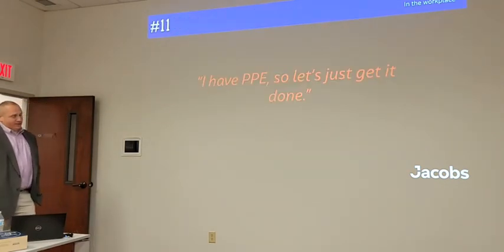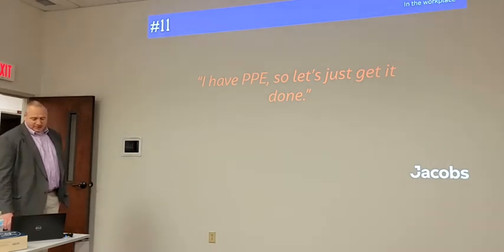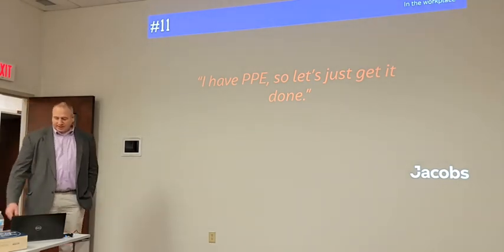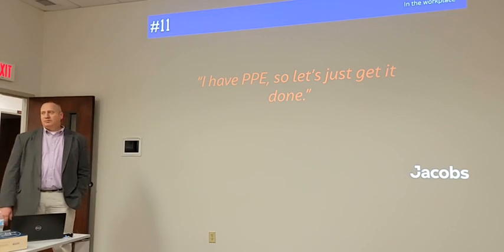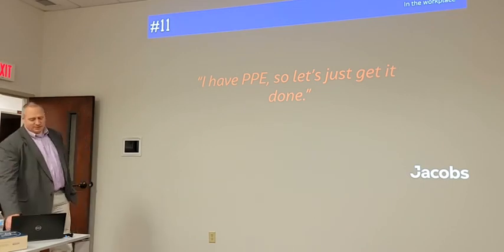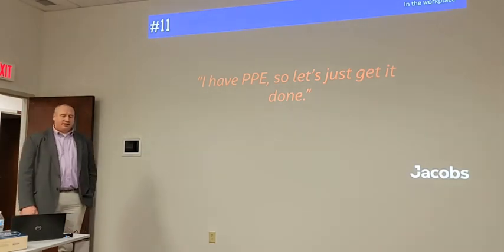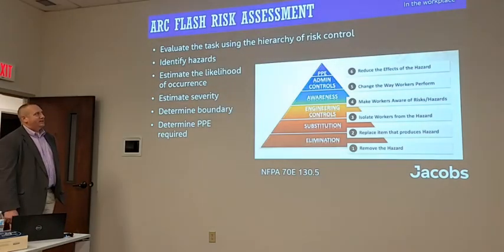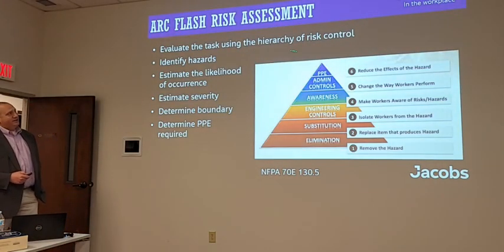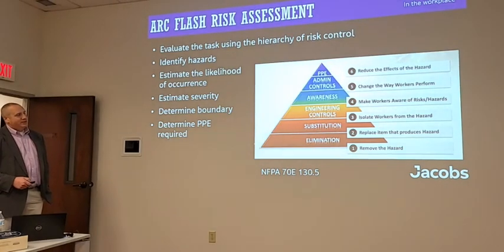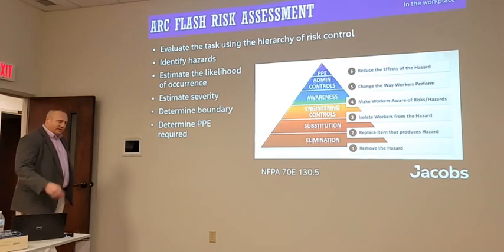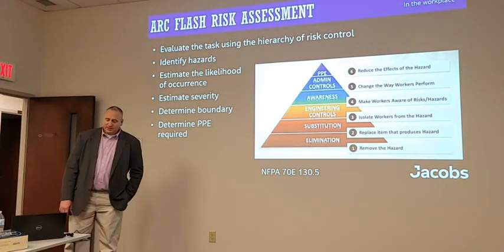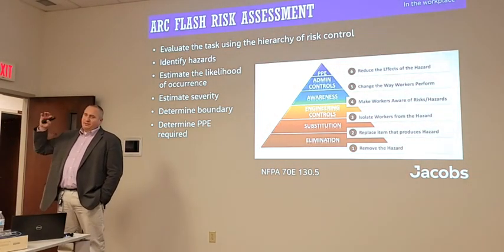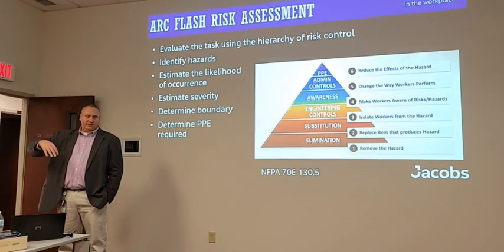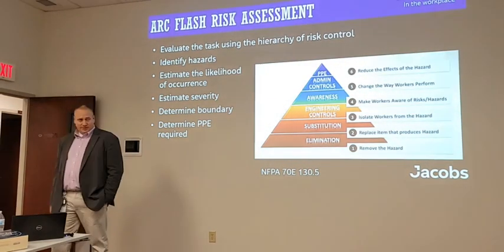So I have PPE, so let's just get it done. And that seems to be the common theme too, of I've got my arc flash PPE, so let's just throw the arc flash PPE on and I'm gonna be protected and I'm gonna start operating breakers. Well, that's not the intent. The intent is to follow the hierarchy of risk control methods to where your most effective approach is to eliminate the hazard. Can you do it with the system de-energized? Is there an upstream device that can be operated remotely that can kill the energy to where you don't ever have to put on arc flash PPE?